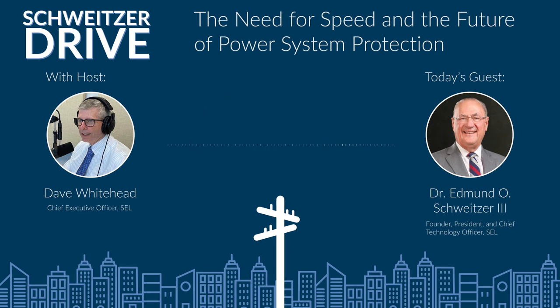Well, our friends who make those are working on DC breakers, and DC breakers don't have to wait around for a current zero to do their interruption. They have to force a current zero somehow, and those things are clearing or interrupting fault current a lot faster than their AC cousins. So I'm glad that we're making the fastest relays in the world, and this, frankly, does put a lot of challenge and opportunity in the hands of our friends who make circuit breakers. Say, hey, for the next big improvement, we're going to need to see a significant reduction in breaker time.